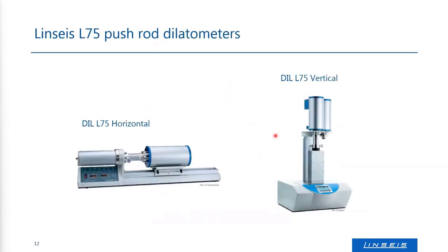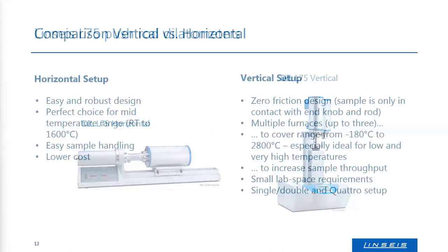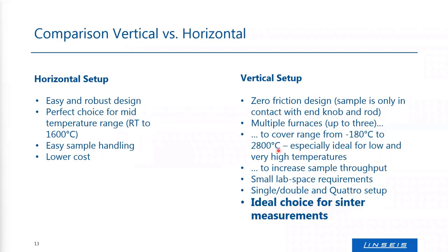We have two kinds of pushrod dilatometers: horizontal ones and vertical ones. Both have advantages and disadvantages. For sintering and for measurements in hydrogen, the vertical systems are preferred. For sintering measurements, it is beneficial if there is no friction on the sample, which is a problem in horizontal pushrod dilatometers.